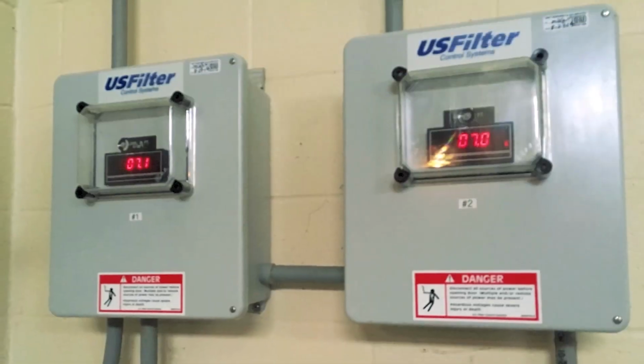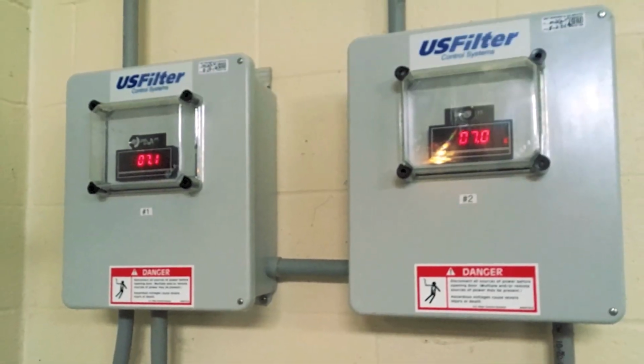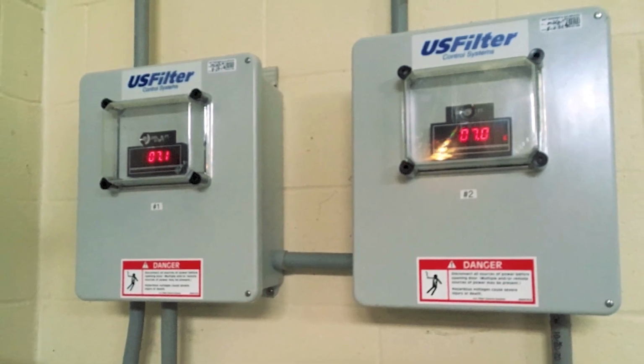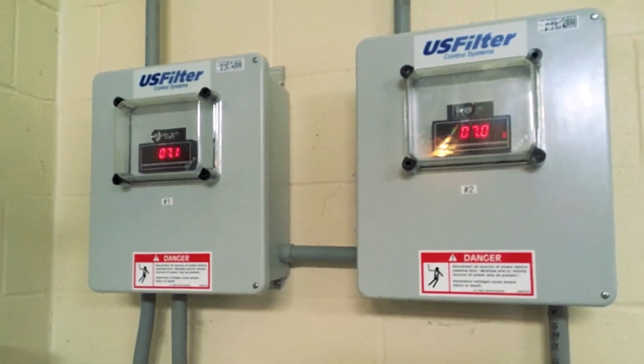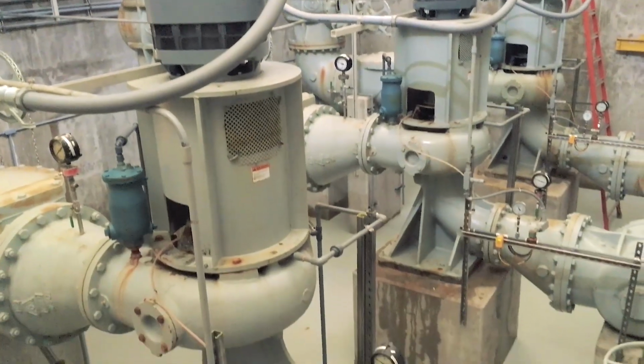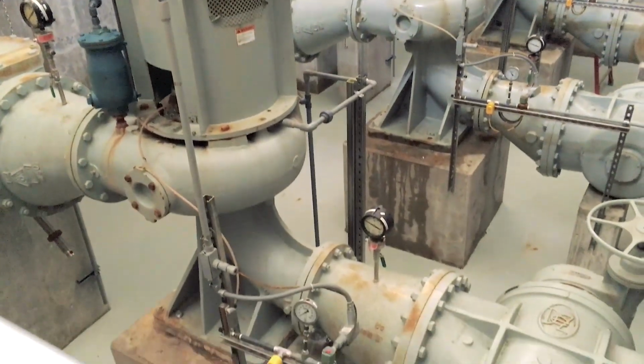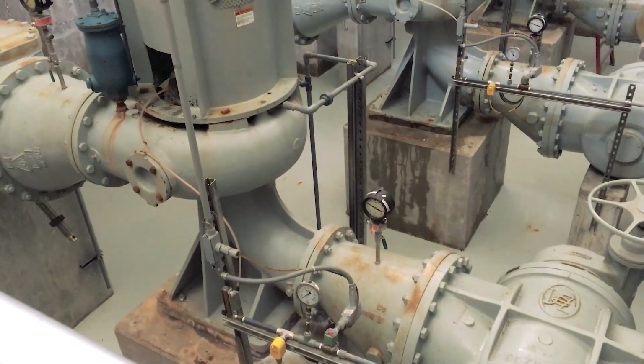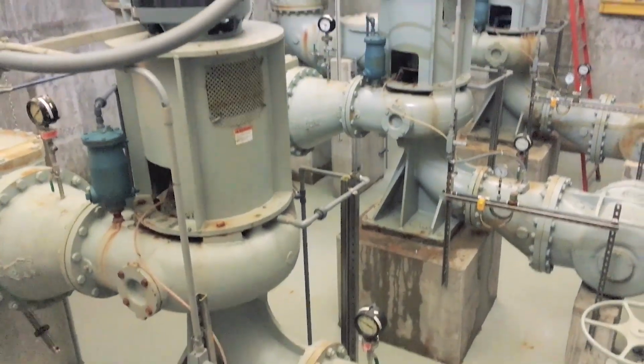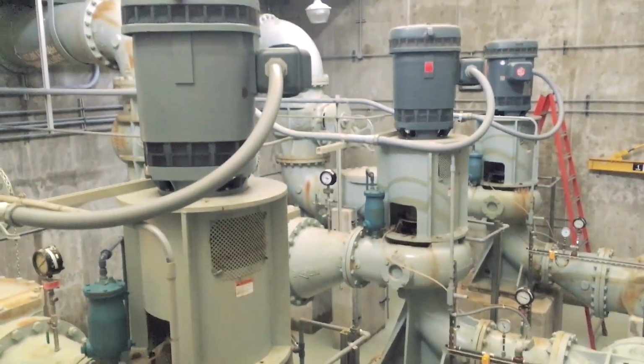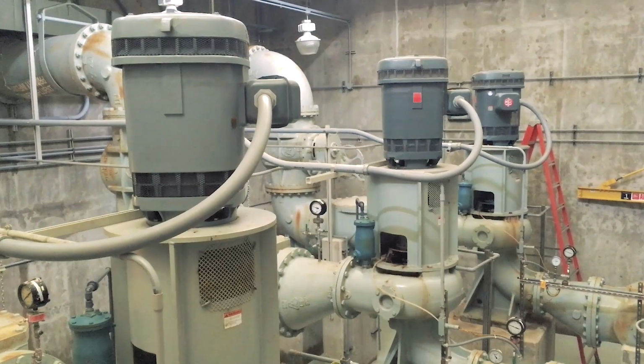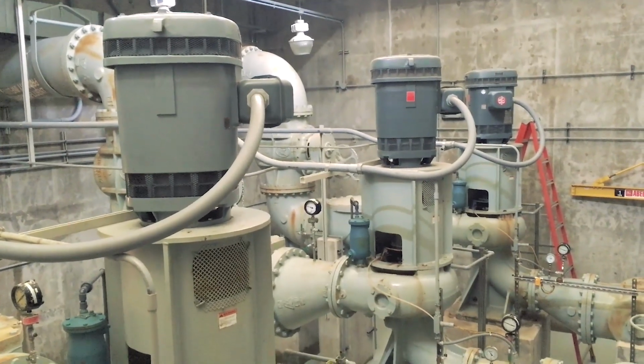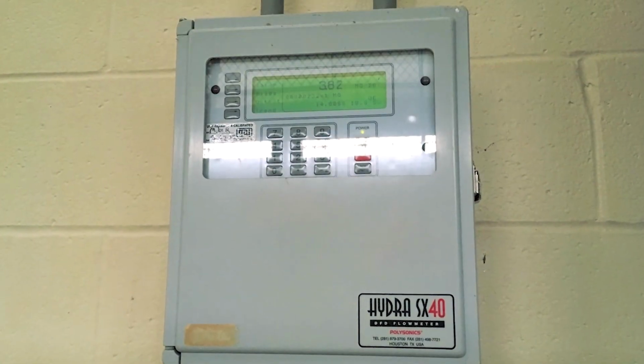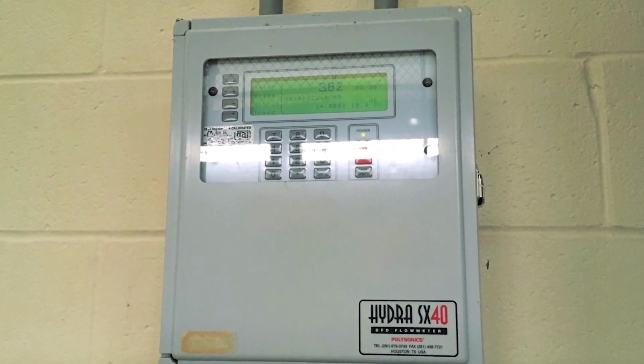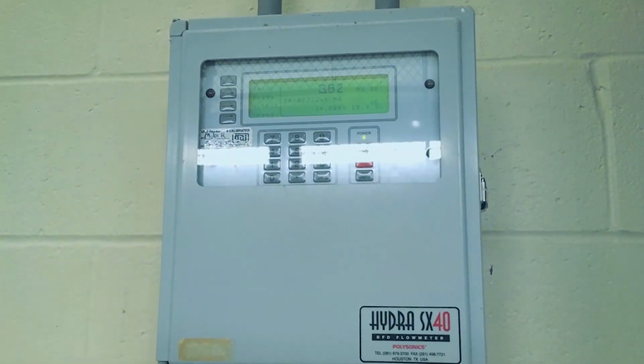The pumps modulate automatically based on water level, which is measured by submersible level transducers in the wet well. Each pump has an accompanying 24-inch isolation, plug, and check valves. Pressure gauges are located on both ends of each pump, and a water seal unit system allows the continuous supply of water to the pump shaft seals. The flow can be monitored by an ultrasonic flow meter located in a manhole outside the building.